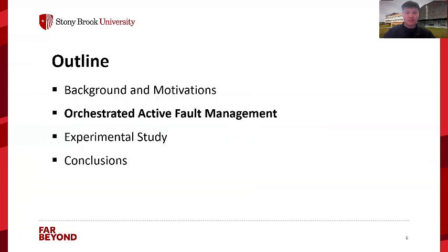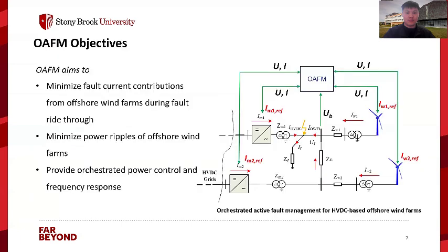Next, I will present the formulation of orchestrated active fault management. OAFM is a multifunctional method and aims to, first, minimize fault current contributions from offshore wind farms during fault ride-through. Second, minimize power ripples of offshore wind inverters. And third, provide orchestrated power control and frequency response.